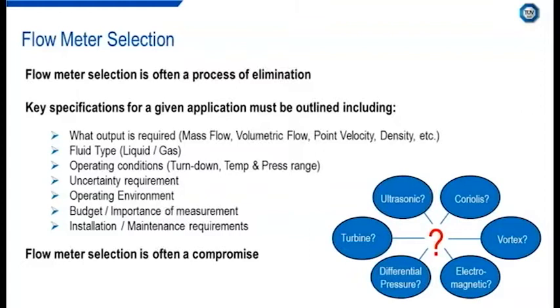The type of fluid being measured: for a liquid application or a gas application, or perhaps for a multiphase metering condition. The fluid type as well as the fluid properties are necessary in order to specify an appropriate flow metering solution or technology. The operating conditions as well are important. The rangeability required for the meter, or the turn-down ratio. All metering technologies have different turn-down ratios, and so the sizing of the meter as well as the number of meters required for the application will result from the turn-down ratio, as well as the temperature and pressure range.